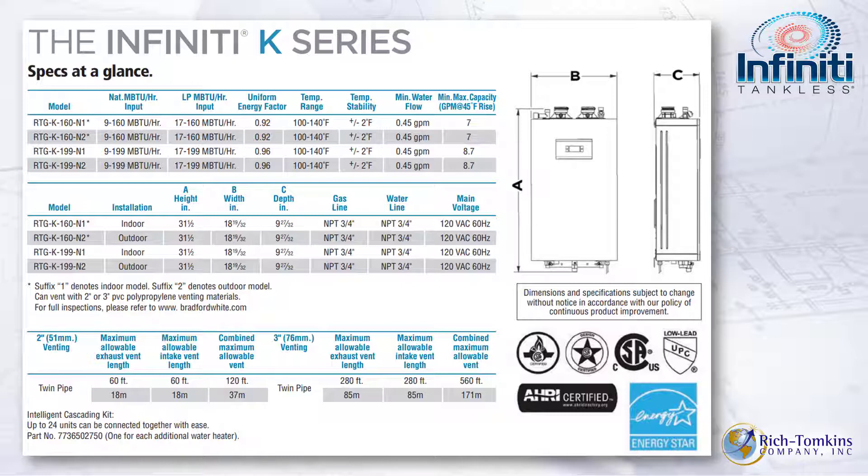We'll get into gas line sizing later, but something to consider when swapping out a tank-type water heater: when replacing it with a wall-hung tankless like the Infiniti K, you have to look at your gas connection. Typically a tank-type uses half-inch, while the Infiniti K requires 3/4-inch. You must adapt to the 3/4-inch and, most importantly, meet the minimum inches of water column gas pressure for the unit, whether natural gas or LP.